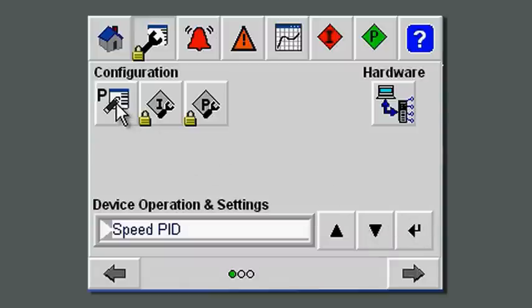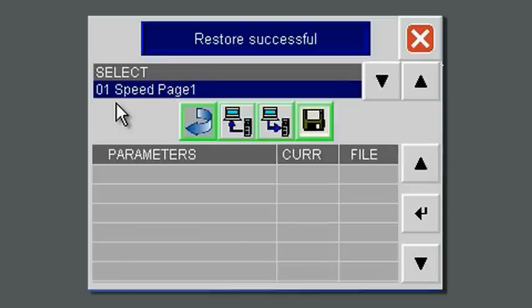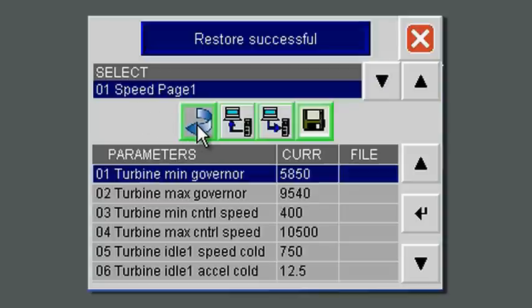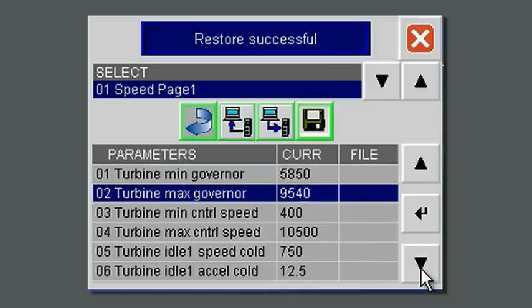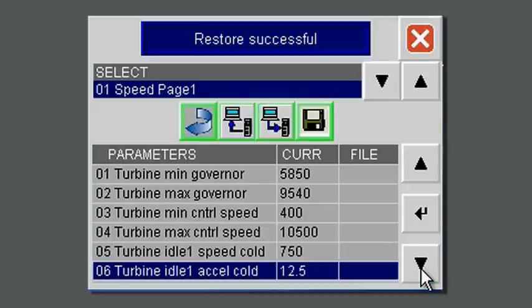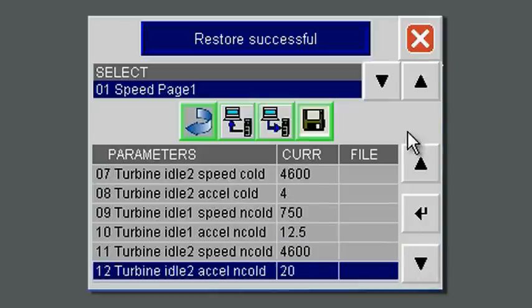Changes are made from the parameters page when you have adequate clearance in engineer mode. When you come into the actual recipe, which is where the menu configuration is, you can read what's in the controller and take a look at the information available on the particular configuration as currently being used. This information can be saved to the HMI, downloaded to the controller, or uploaded from the controller — all of those options are shown on the menu. As you move through the menu, you see the different configuration items for the turbine, each of which can be configured for your particular installation.